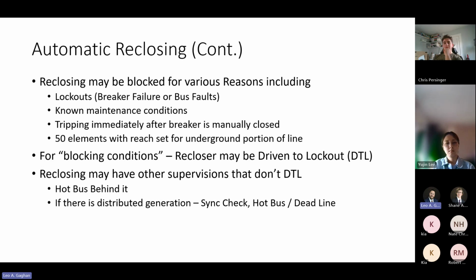Sometimes you may only want to close on a hot bus behind you and a dead line in front of you. Sometimes you can close if you've got a hot bus and a hot line, but then you want to do something called a sync check, which means that those sine waves are lining up with each other. So there's a good amount to consider here. We're doing a high level look at the whole thing right now, but there are a lot of details to consider if you're doing different protection designs.